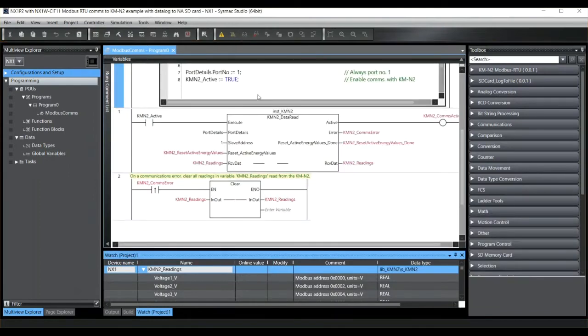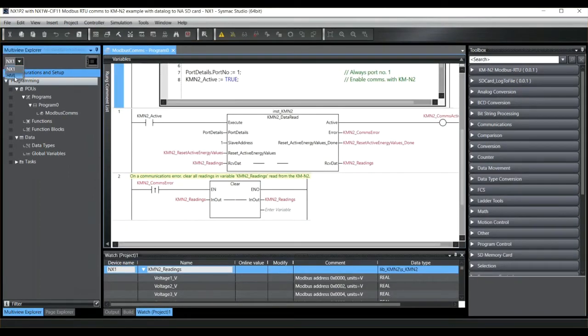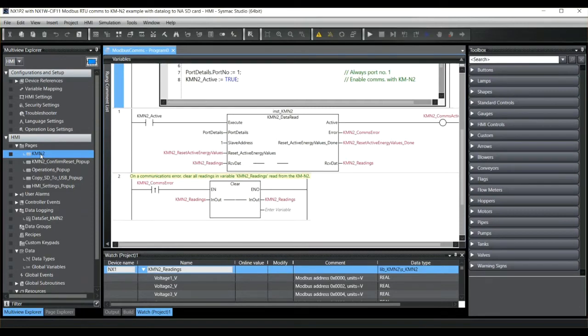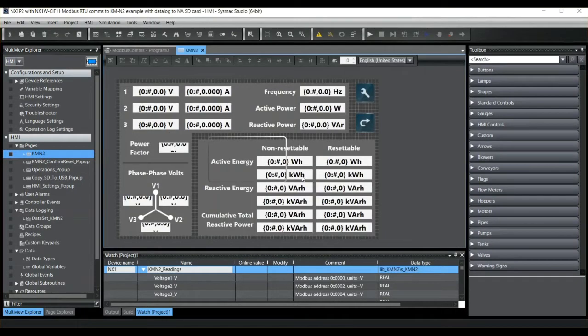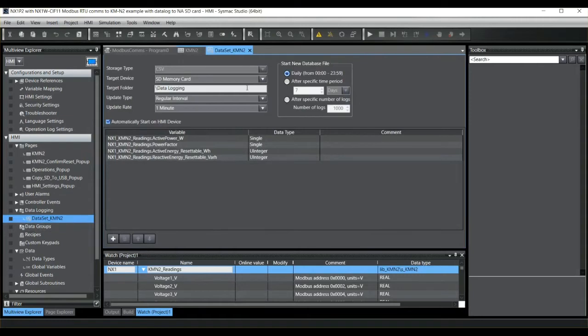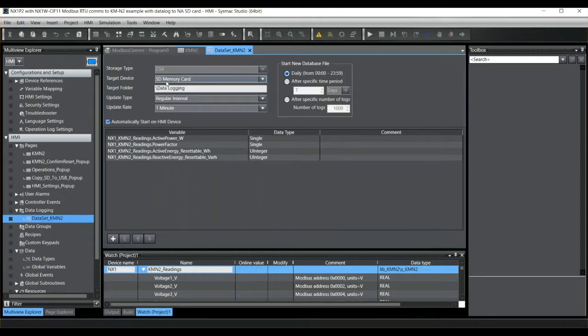If I come offline from the NX1P2, in this project I also have an NA Series HMI — this one being a 9-inch model. The main page shows all the readings coming from the KMN2, and we can data log these. To do that, under data logging we set up a data set. I've created a data set here called DataSet KMN2. Storage type is always to CSV files, and we can specify whether to save those files to SD memory card or to the USB stick plugged into the HMI. The reason I've chosen SD memory card is that if you choose USB memory stick, then that memory stick must be plugged in at all times, otherwise the data logging stops.